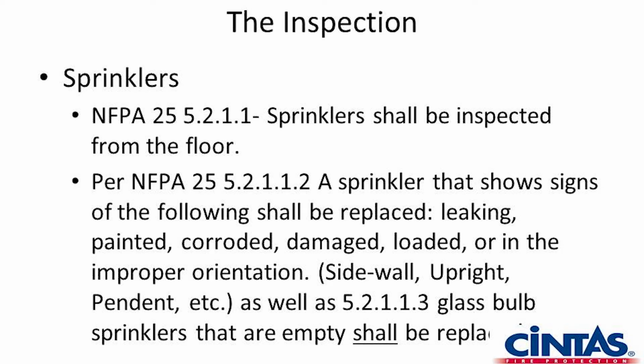Corroded sprinklers: if you get a quote, or as you are visiting your facilities, this happens a lot around swimming pools, where water softeners are stored in those rooms. The corrosion happens at the seat of the sprinkler, and this is much easier if we were live. Hopefully one day we will have the opportunity to be live with each other on site, and I can show you. But what happens is that corrosion grows across the seat of the sprinkler.